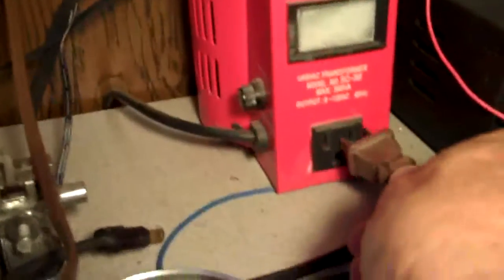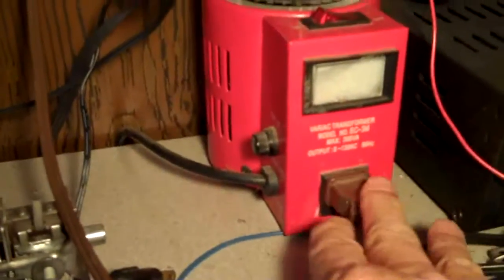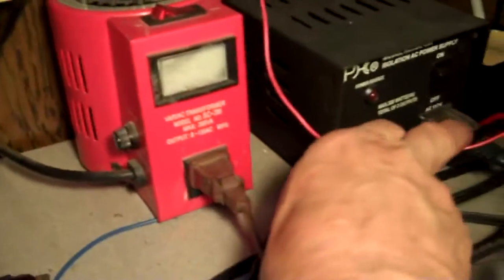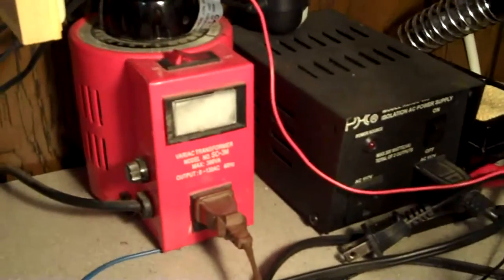This plug right here is a wire as you can see and it goes up inside the box. This wire plugs into the variac. The variac, this wire right here going out of the variac, goes over and plugs into the isolation transformer, which is right - that's the plug right there. And the isolation transformer plugs into the wall. So from the wall to the isolation transformer, to the variac, to the box.